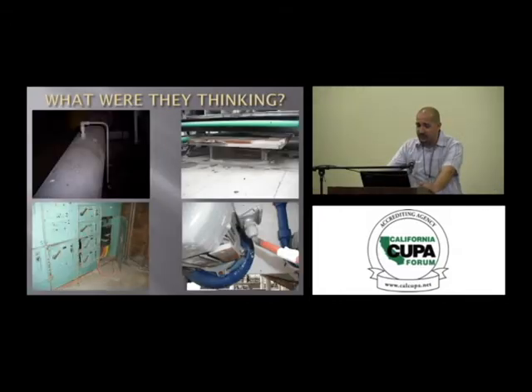And that is, of course, as you can see, what's the issue there? That's inside of a compressor room. Kind of covered that already, I guess. That's just not properly venting. If you're standing next to that, seems to be a thermosiphon, maybe a thermosiphon oil cooler. That's correct. That is going to spew probably oil, and oil is going to have a high concentration of ammonia, so whoever's in the area is going to get quite a shock when that pops off.